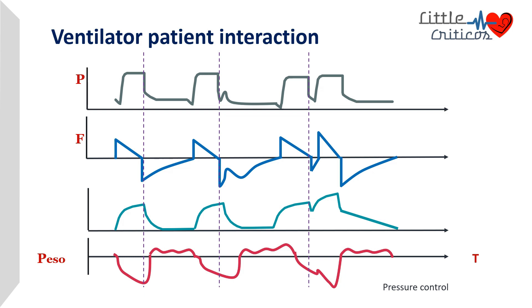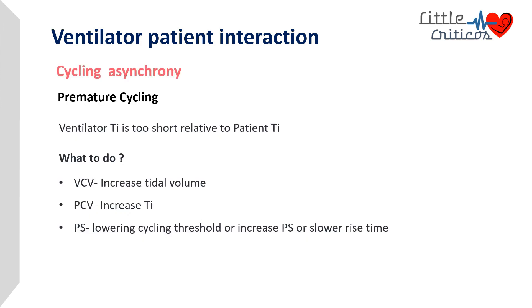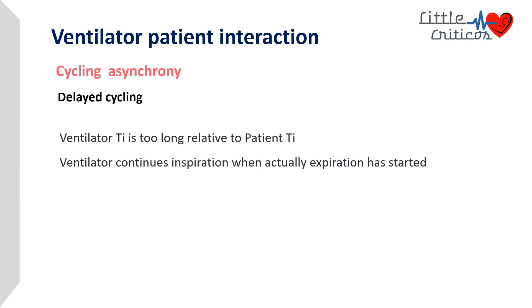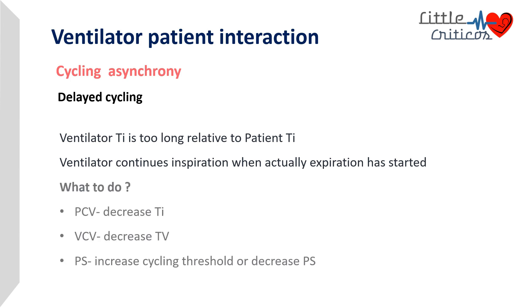Though classically described as double triggering, it is actually the result of premature cycling. To overcome premature cycling in volume-control mode, increasing tidal volume can increase inspiratory time. In pressure support, lowering the cycle threshold, increasing pressure support, or using a slower rise time can help reduce premature cycling. Delayed cycling results when the ventilator inspiratory time is too long relative to the patient's inspiratory time. It can be overcome by decreasing inspiratory time in pressure-control ventilation, decreasing tidal volumes in volume-control ventilation, and increasing the cycling threshold in pressure-support mode.